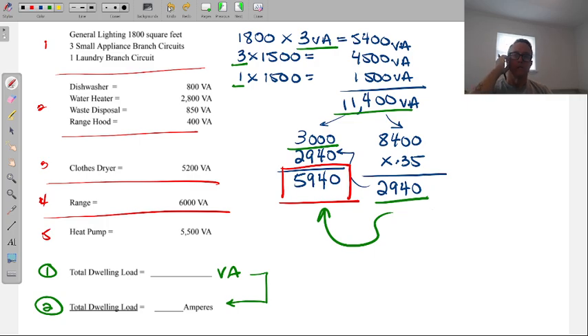Is it over 20,000? So what started off as 11,400 VA ends up at 5,940 VA for our panel. And so that becomes, remember, these are not, we'll get to our total, but this is for the first section, the number we're running with. And this, now you can complete section 2, 3, 4, continue on through. Each section has to be, bless you, done correctly.